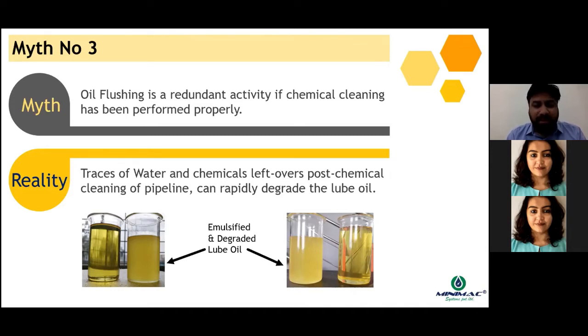It has been seen multiple times by the commissioning engineers that whenever they start their lube oil system after performing the chemical cleaning activity, if the flushing was not done properly or it was ignored completely, the first time run of the lube oil system might have a risk of the oil getting mixed with the chemicals or with the water which had been used during the chemical cleaning process.